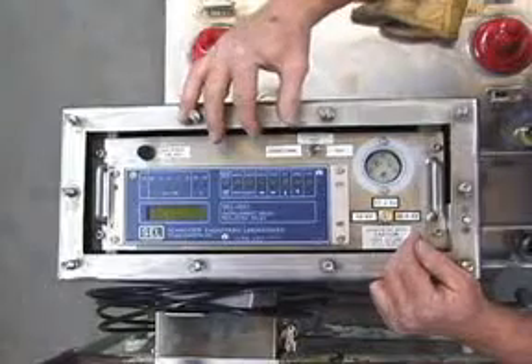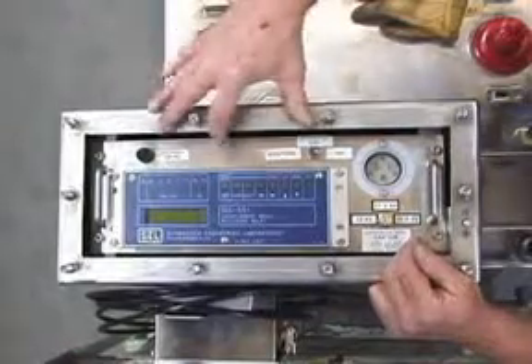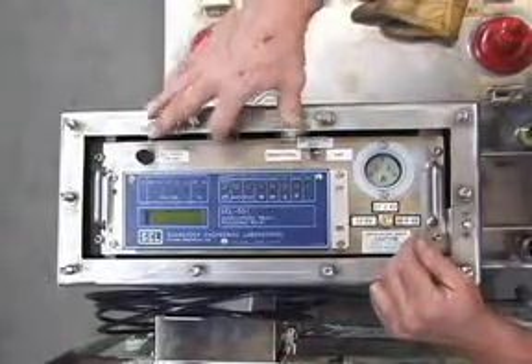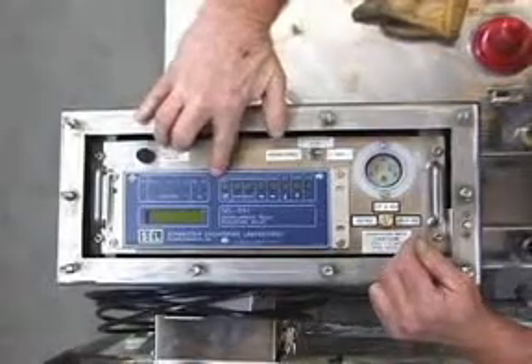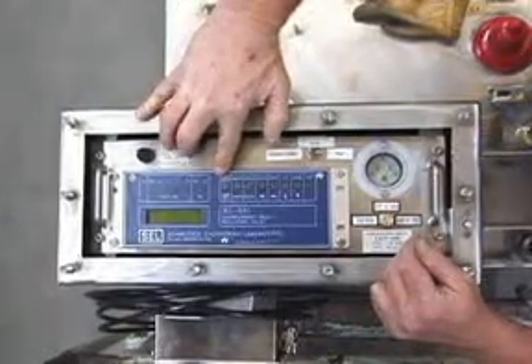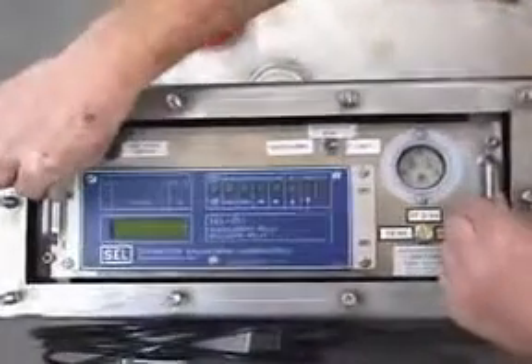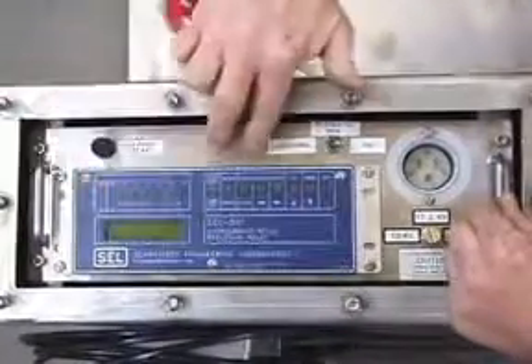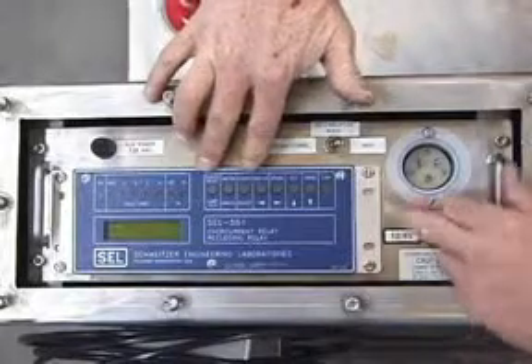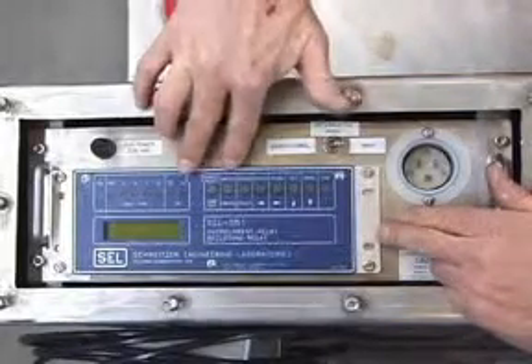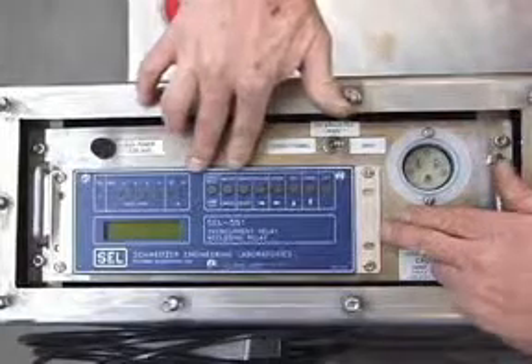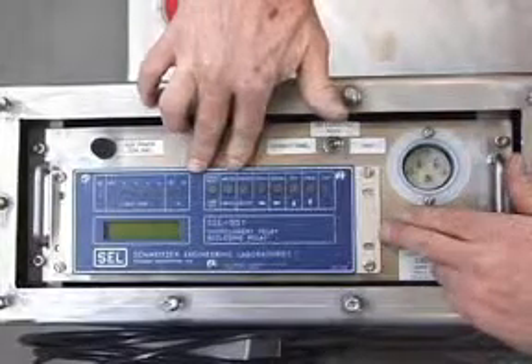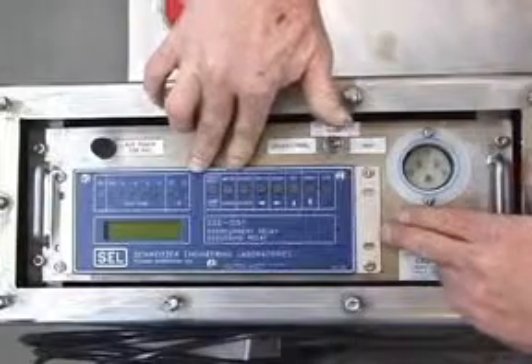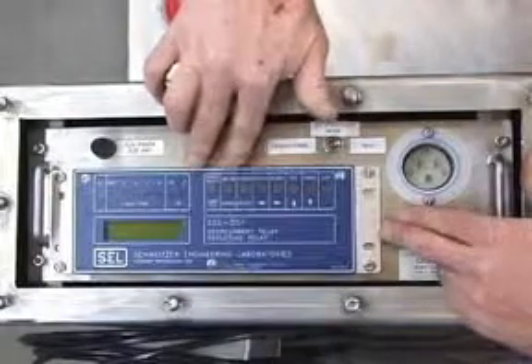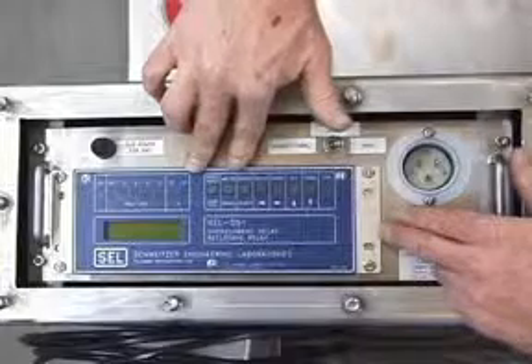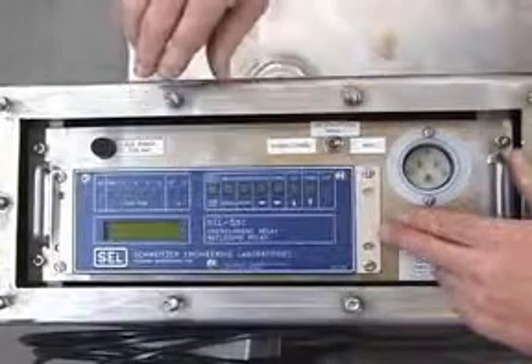Here's a view inside of the relay compartment of our submersible fault interrupter. Utilizing an SEL 551 microprocessor type relay in a draw-out panel for easy service. At Trayer, we prefer to use a commonly available relay system that most of your relay engineers have been trained on and are familiar with, as opposed to using proprietary electronics. We feel that this gives the owner of the equipment greater flexibility for service.